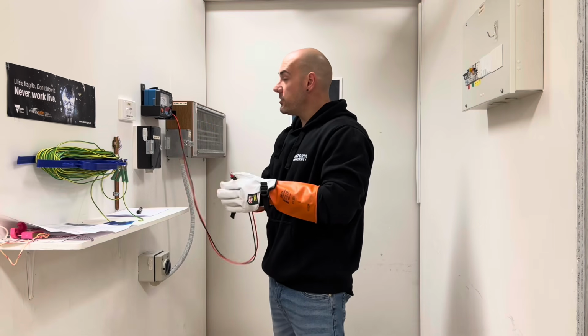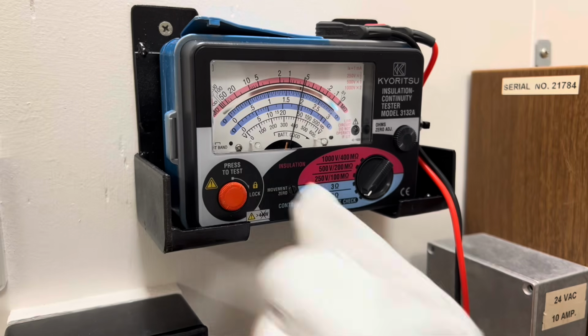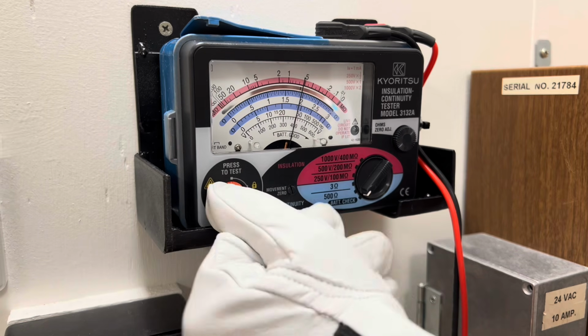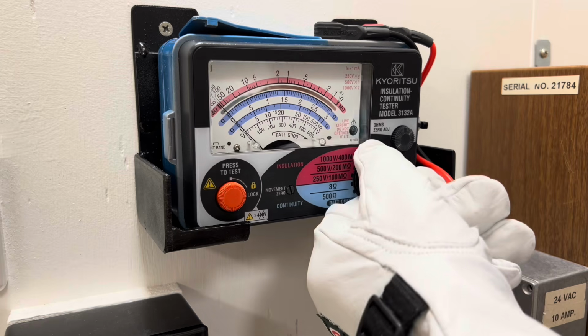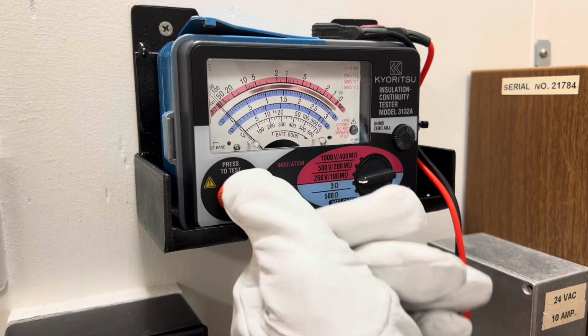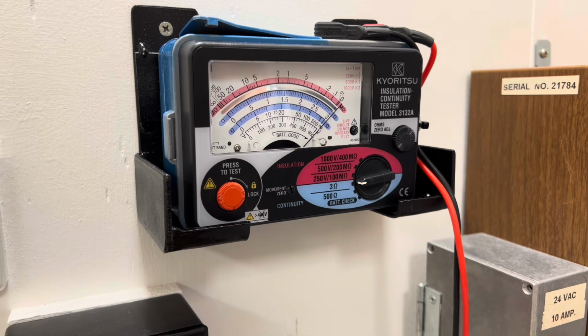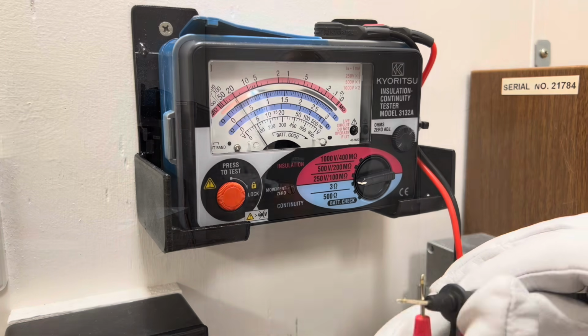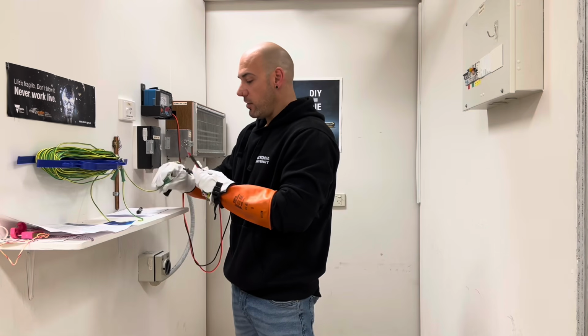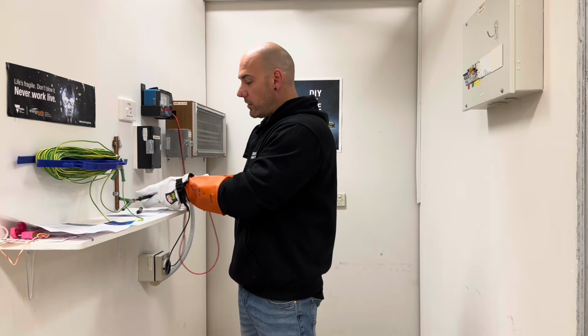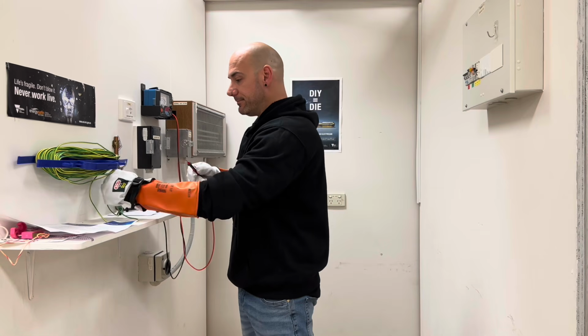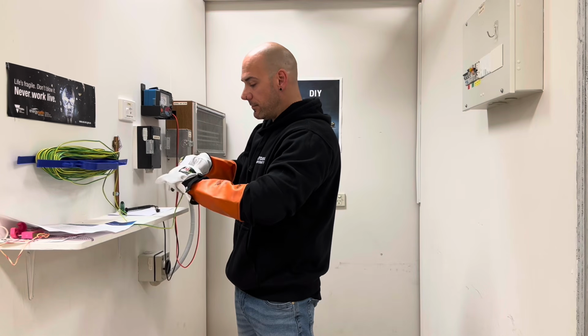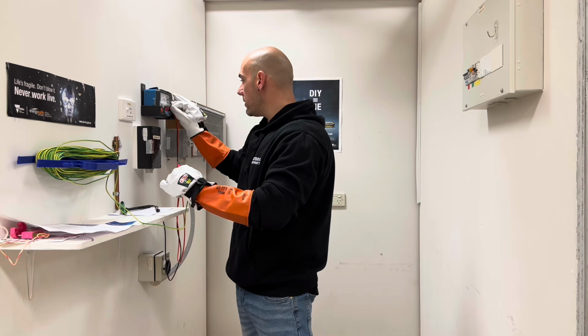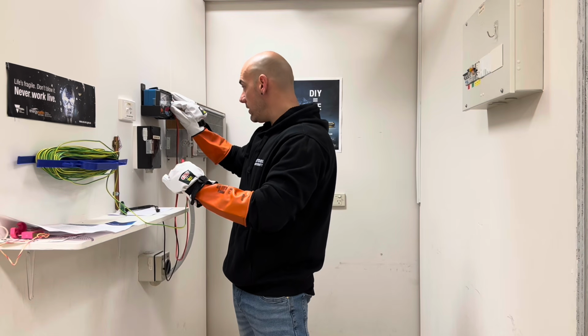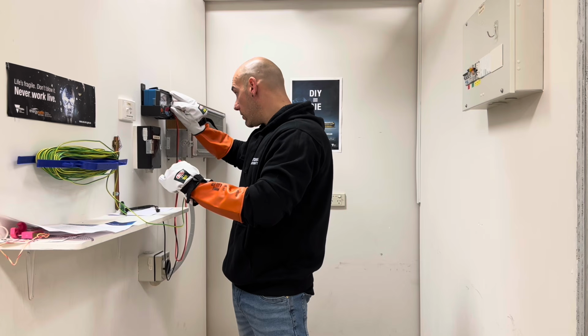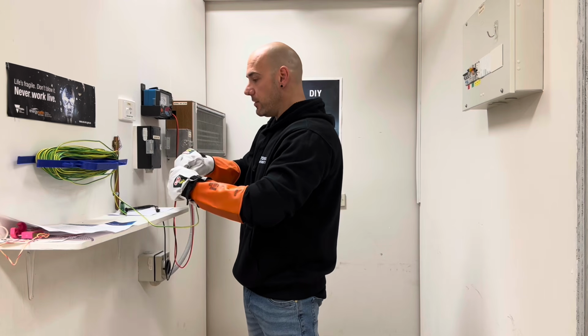I'm going to do a battery check on our IR tester. It's within the good battery range. Go over to the 3 ohm scale, make sure our meter is working and it is calibrated. Great. I'm going to connect the trailing lead to our IR tester, and zero our meter to make sure any resistance from the trailing lead is removed. Okay, that's on 0. Beautiful.